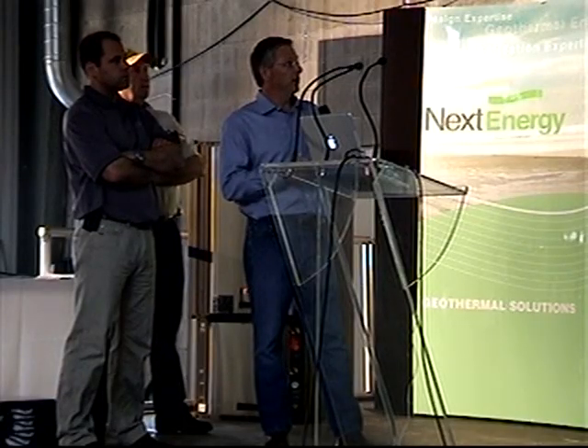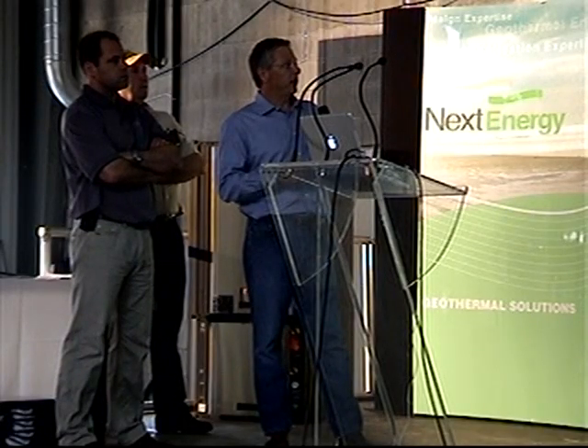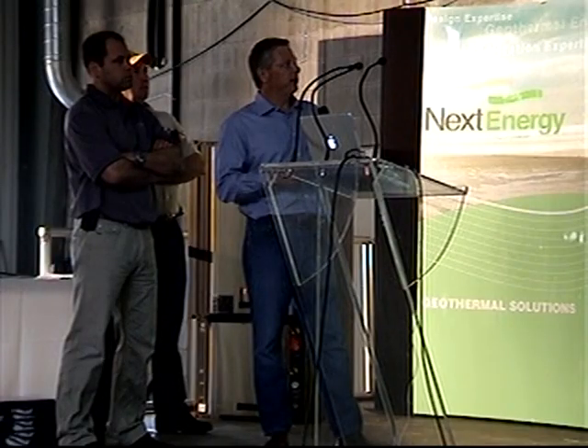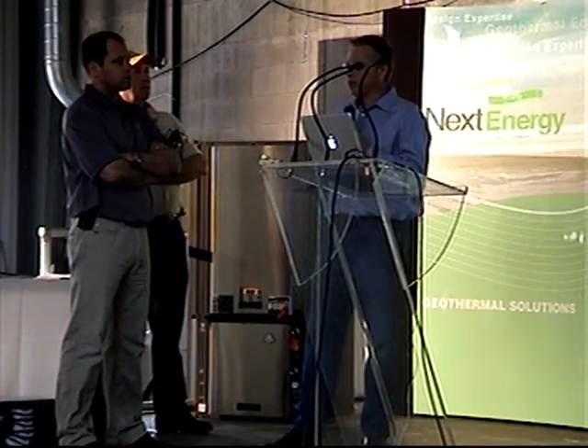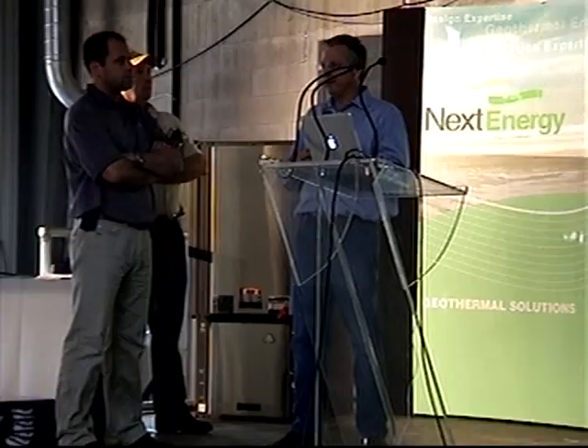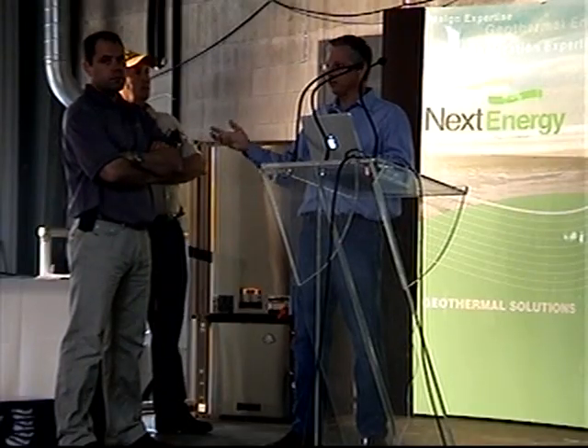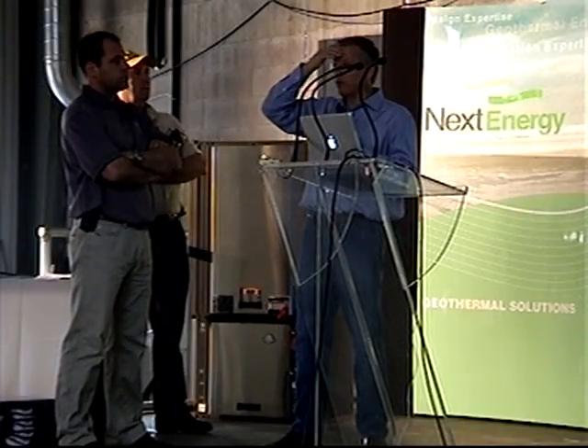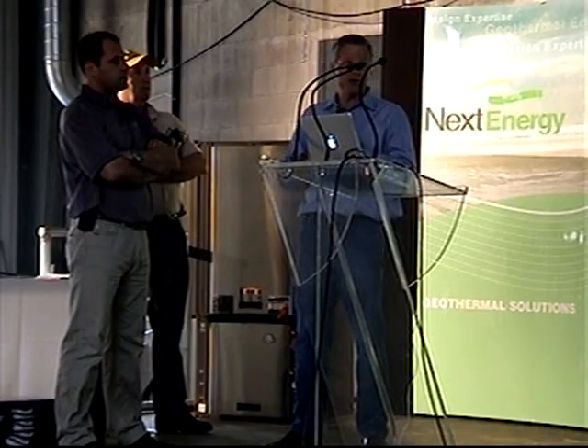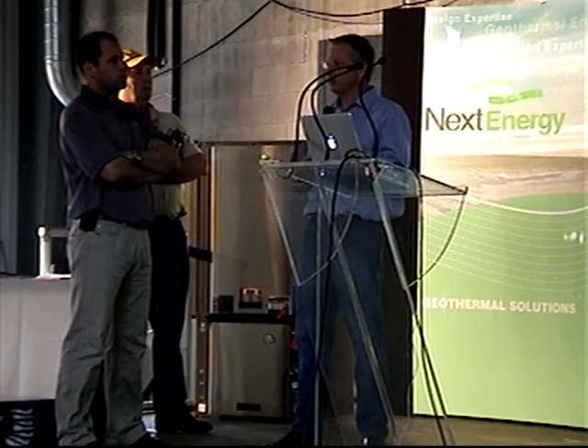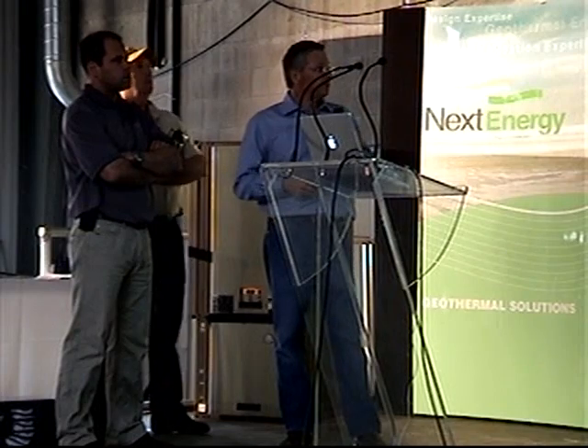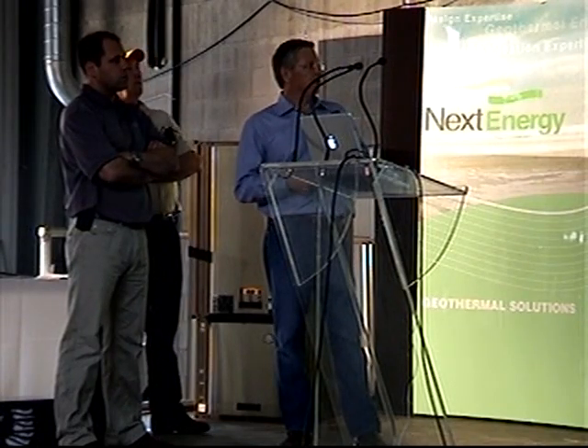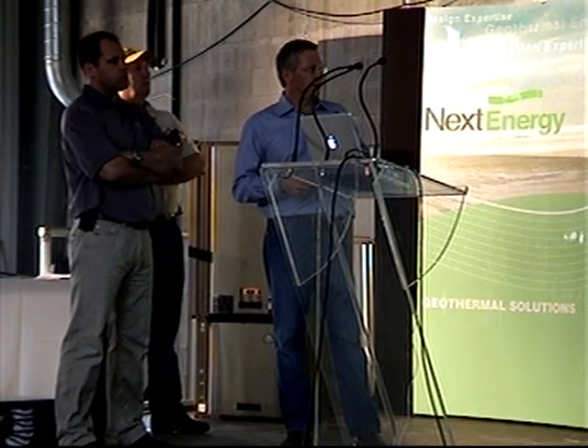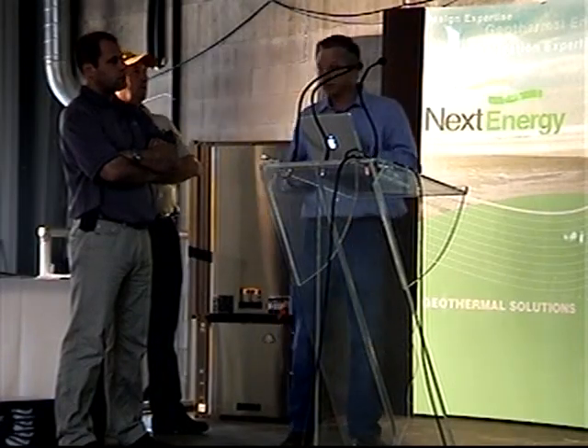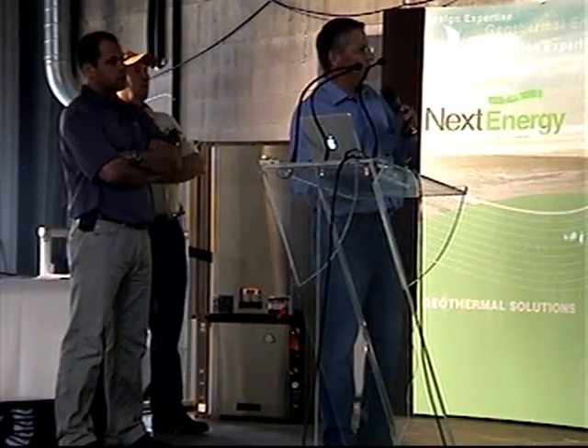There is a fault memory in it. So if the unit does lock out and the breaker hasn't been reset, it'll remember the last reason the unit locked out. It doesn't have a battery, so it won't remember if power's been off. And then there are some accessory relay terminals to provide for air cleaners, humidifiers, and water valves for a well system.